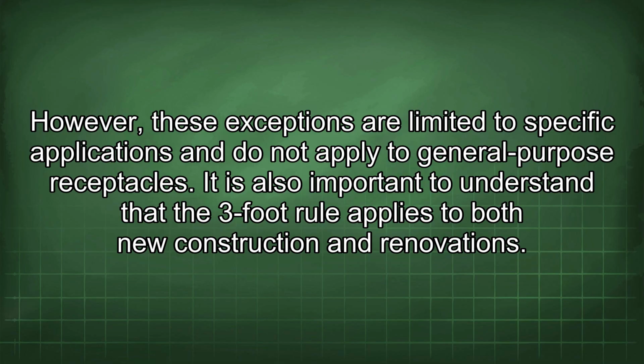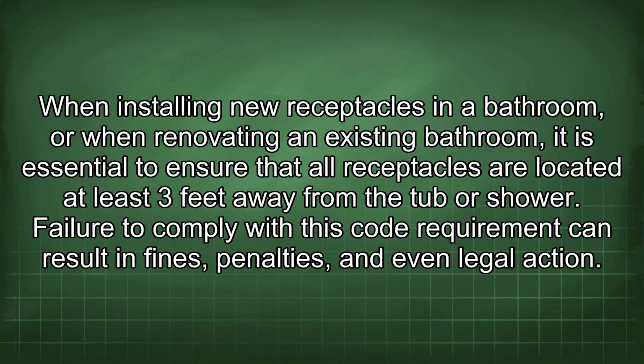It is also important to understand that the 3-foot rule applies to both new construction and renovations. When installing new receptacles in a bathroom or when renovating an existing bathroom, it is essential to ensure that all receptacles are located at least 3 feet away from the tub or shower. Failure to comply with this code requirement can result in fines, penalties, and even legal action.